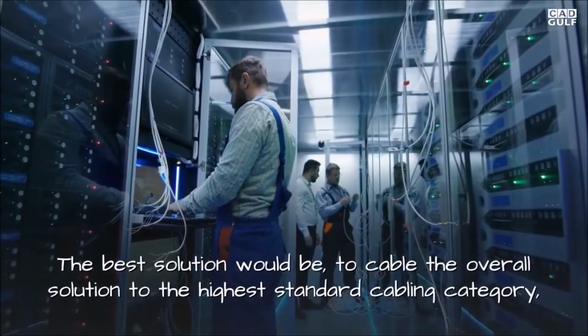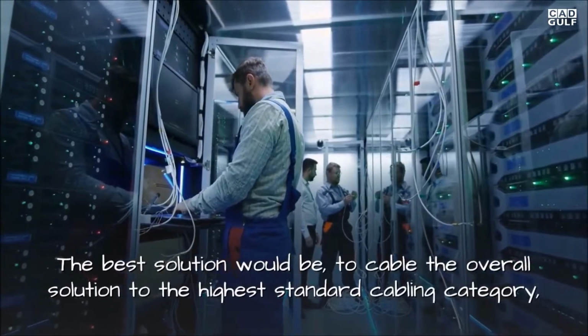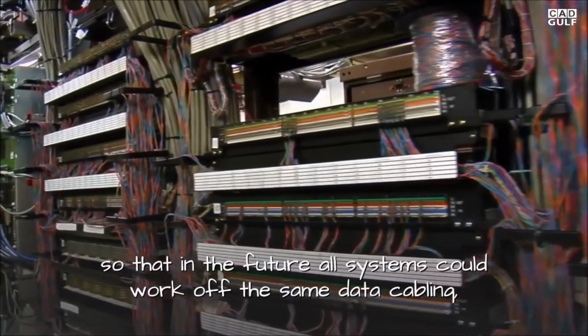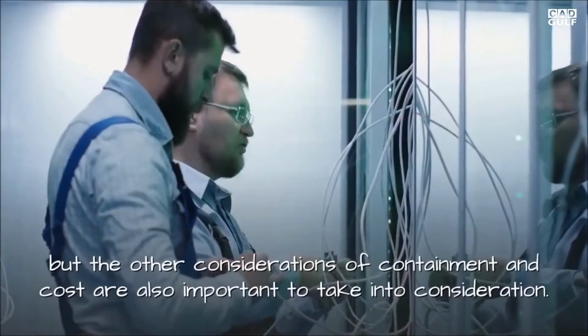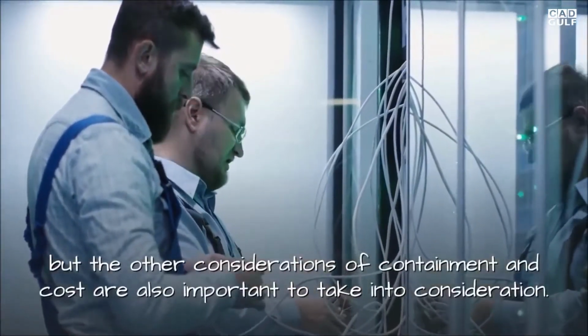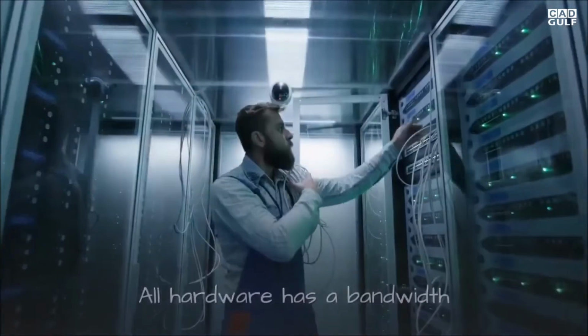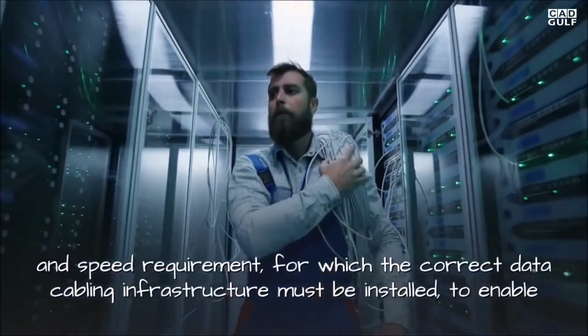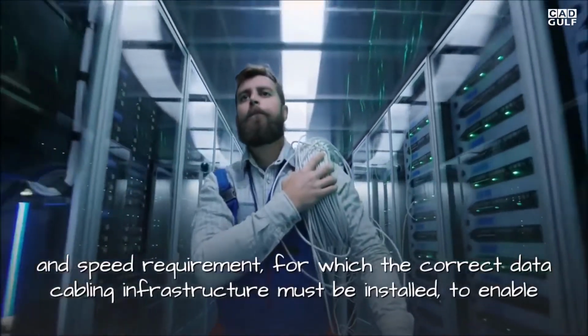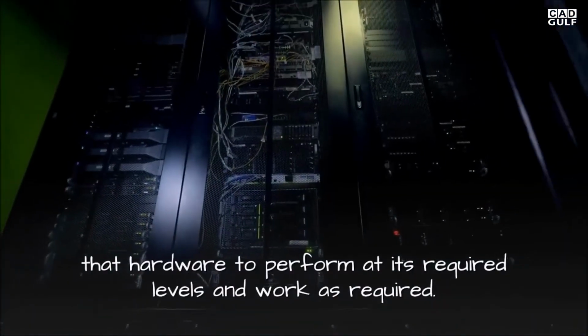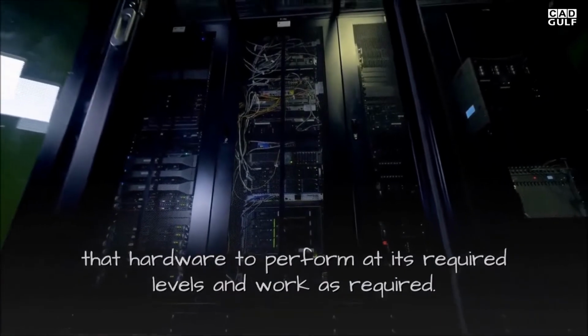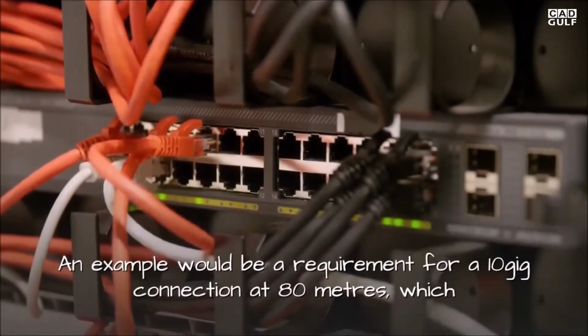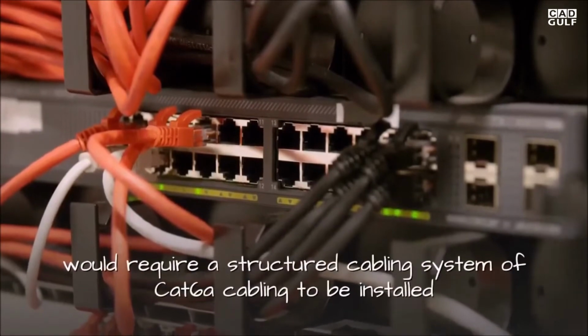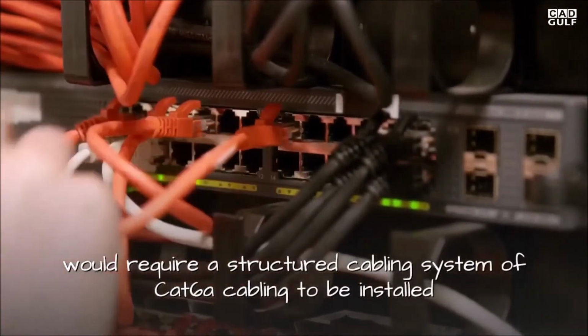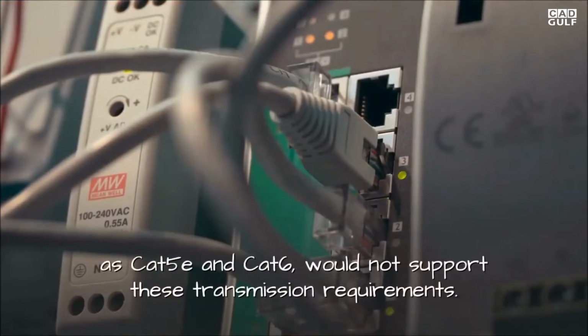The best solution would be to cable the overall solution to the highest standard cabling category, so that in the future all systems could work off the same data cabling, but the other considerations of containment and cost are also important to take into consideration. All hardware has a bandwidth and speed requirement, for which the correct data cabling infrastructure must be installed, to enable that hardware to perform at its required levels and work as required. An example would be a requirement for a 10 gig connection at 80 meters, which would require a structured cabling system of Cat6a cabling to be installed, as Cat5e and Cat6 would not support these transmission requirements.